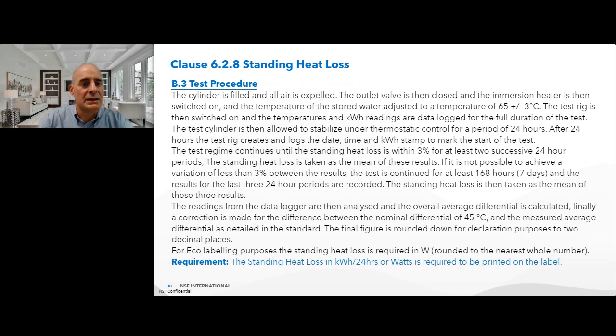The procedure then: the cylinder is filled and all air is expelled. It's important to get all the air out of the cylinder as this will affect the test. The outlet valve is then closed and the immersion heater is switched on, and the temperature of the stored water adjusted to 65 plus or minus 3 degrees. The test rig is then switched on and the temperatures and the kilowatt-hour readings are data logged for the full duration of the test. The test cylinder is then allowed to stabilize under thermostatic control for a period of 24 hours. After 24 hours, the test rig logs the date, time and kilowatt-hour stamps to mark the start of the test.